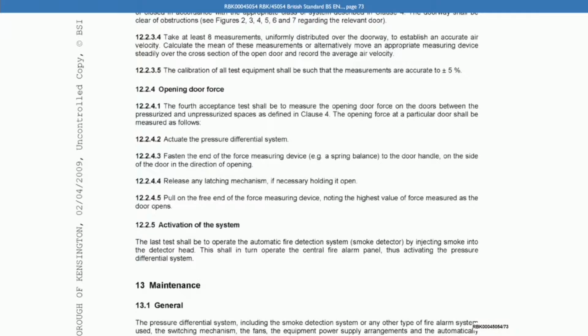Then we can see the method described below that. You have to actuate the pressure differential system, fasten the end of the force measuring device, e.g. a spring balance, to the door handle on the side of the door in the direction of opening, release any latching mechanism if necessary holding it open, pull on the free end of the force measuring device, noting the highest value of force measured as the door opens. Now, were you familiar with that method of testing that door opening force? Yes.